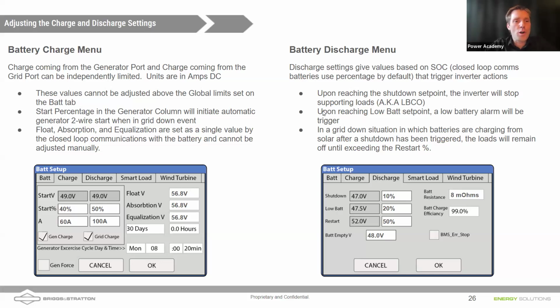So let's look at the battery charge menu. Notice on the setup, we've gone to the next tab over. That's the charge. Here is where we can independently set charging from AC sources, the charging from power coming from the generator port. I'm just going to highlight here with my mouse. Hopefully you can see that. On the generator charge side of things, that's the generator port. So if I have a generator hooked up to the generator port, this would control my overall charge rate from the generator.